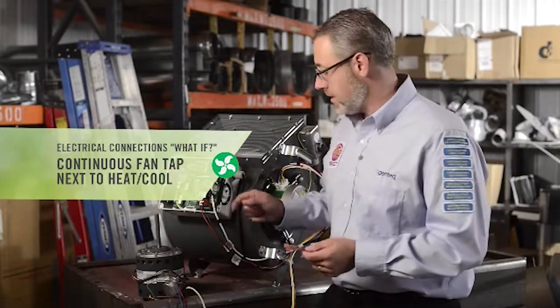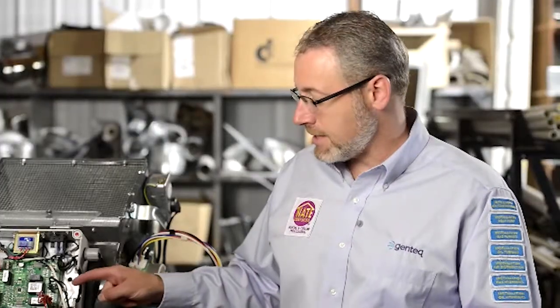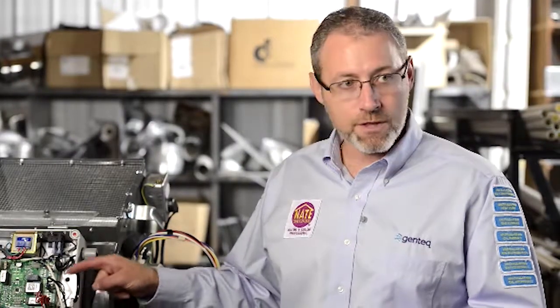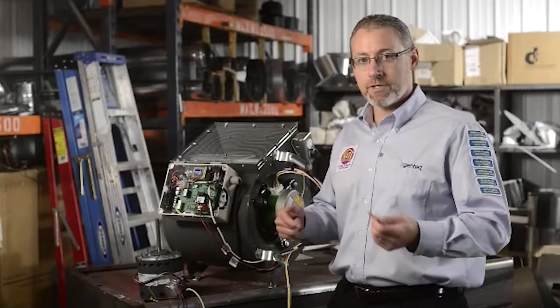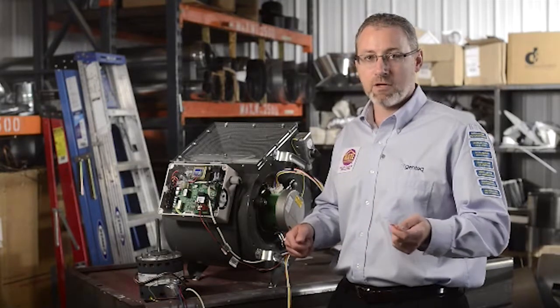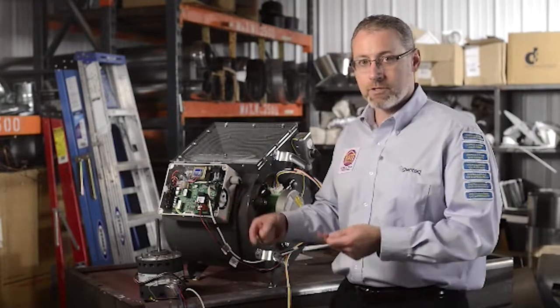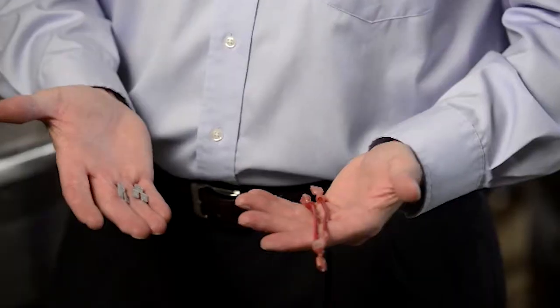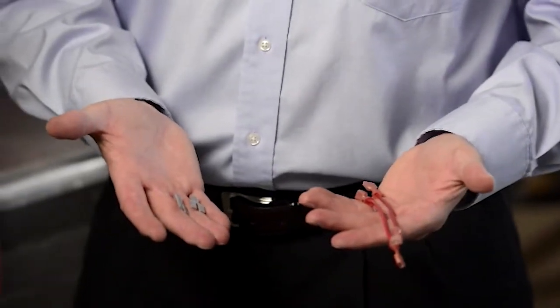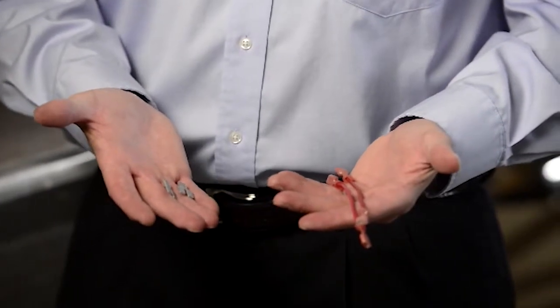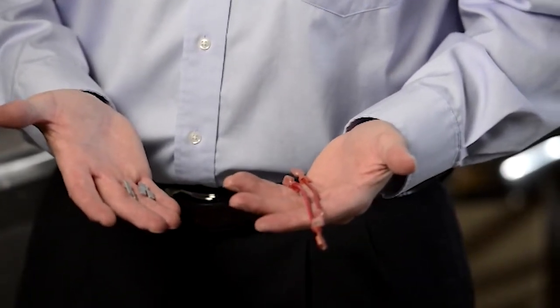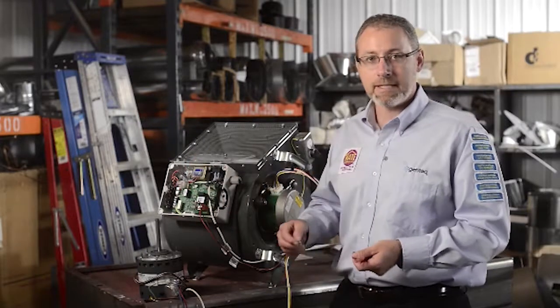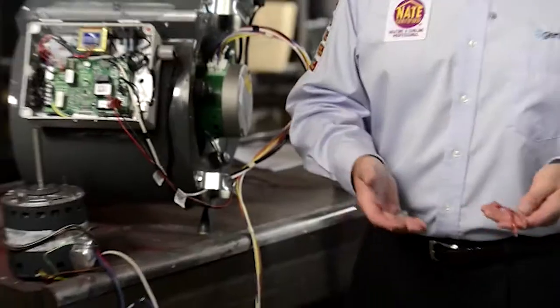So what if there is a continuous fan tap on the control board next to heat and cool? We would need to connect that continuous fan terminal together with the heat and cool terminals so that when the customer turns on the continuous fan setting on their thermostat, they turn on the motor and select the right horsepower. If you remember, in the box we have extra jumper wires and extra 1/4-inch terminal Y connectors. So these extra terminals and wires are going to allow us to jumper in that continuous fan tap if needed. So another what if that you might find is a 2-stage furnace or a 2-stage air conditioner.